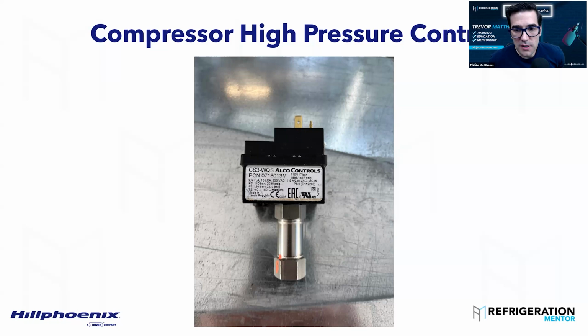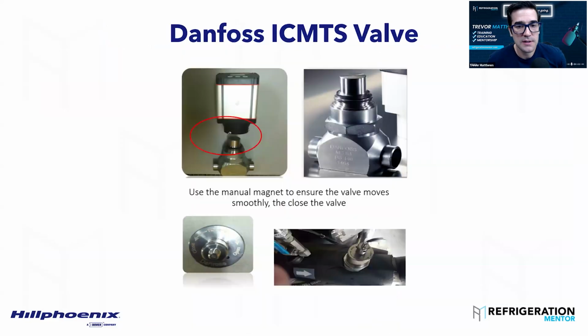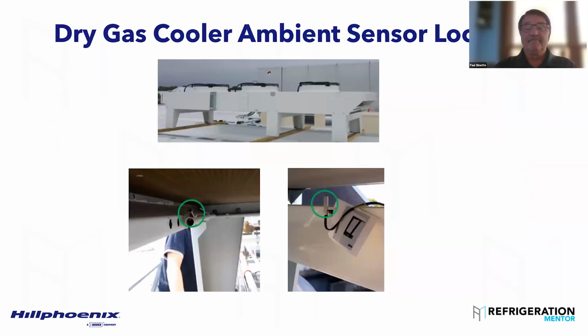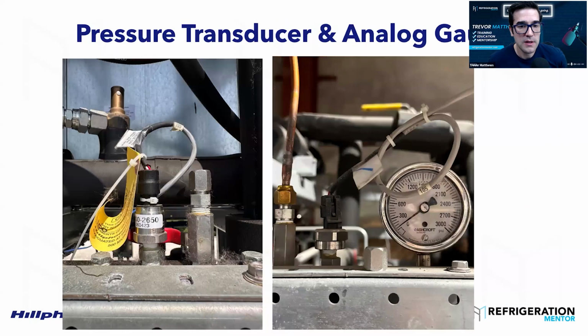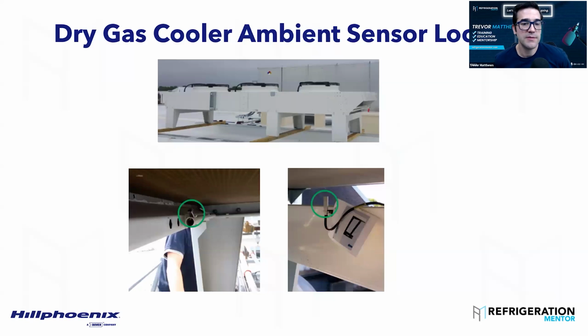Yeah, look there. So shutting off the discharge valve on any compressor is not the way to test at high pressures, regardless of the refrigerant. So there's some people in the box. So thank you. Okay, so very good, big tips there. Fantastic. Okay, so next slide, we're talking about the gas cooler sensor locations.